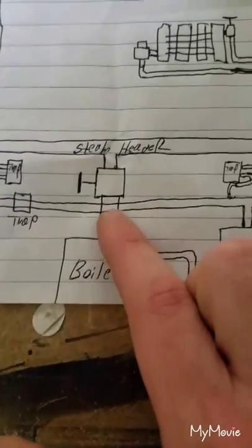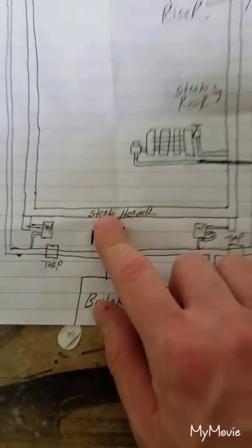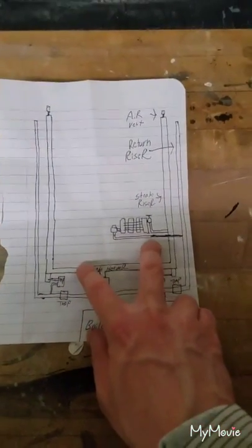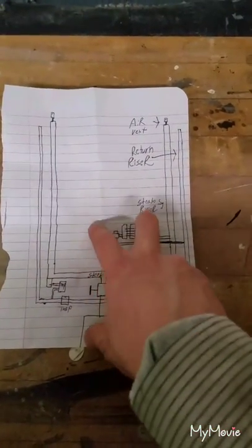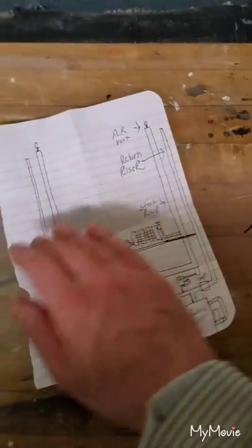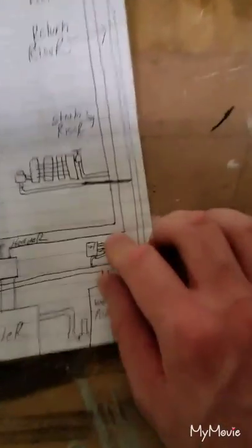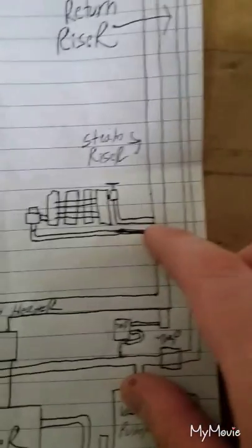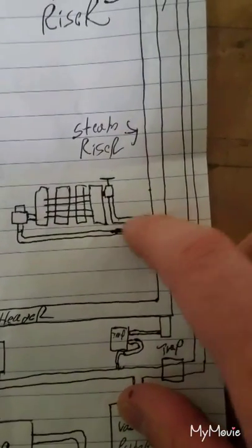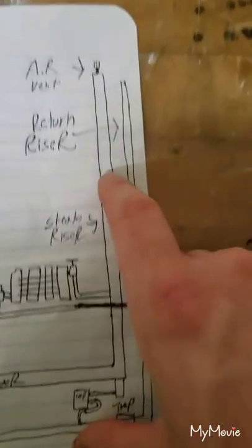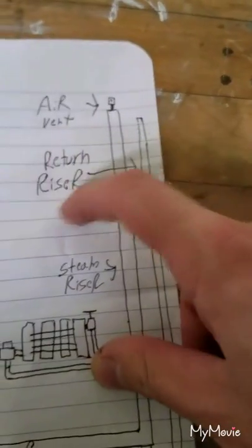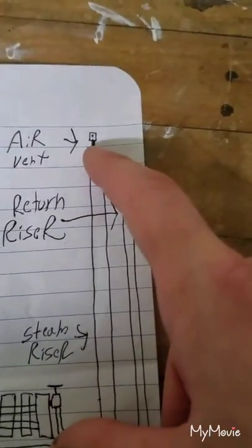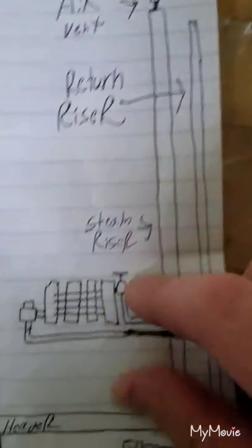The boiler makes steam, comes up here to the steam header. The steam header branches off. Say this building has two apartments per floor. So you'll have an A line and a B line, okay? So the A line, this is the steam, comes up, branches off at the first radiator, continues all the way up to the top, branching off. There's an air vent at the top to help the steam get up quicker.